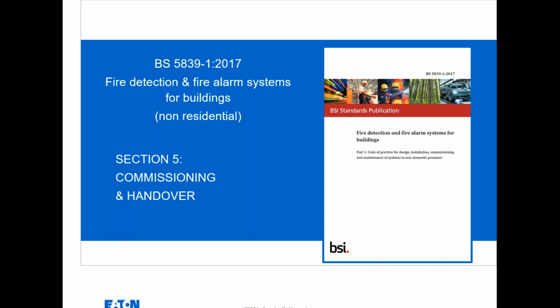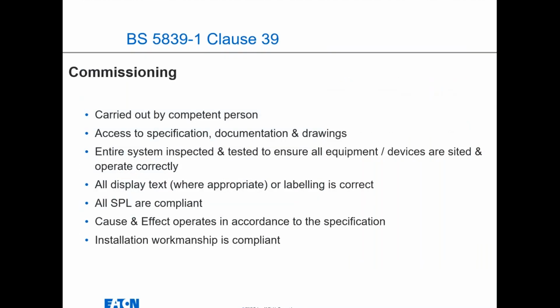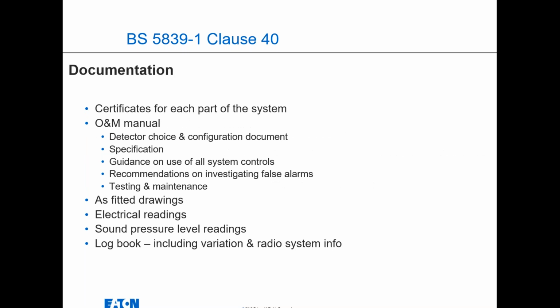And then finally, in the commissioning and handover, this is where the documentation comes in. The commissioning should be carried out by a competent person. So whether that's a conventional system, a by-wire system, or an addressable system, a competent person should be carrying out the commissioning and providing a commissioning certificate, to make sure that everything's installed correctly. Because if you don't have that commissioning certificate, the system is almost deemed non-compliant. So documentation we talked about earlier includes certificates for each part of the system, the O&M manual, as fitted drawings, any relevant electrical readings, the sound pressure levels if that needs to be done, and the logbook including variations and any radio system information, etc.